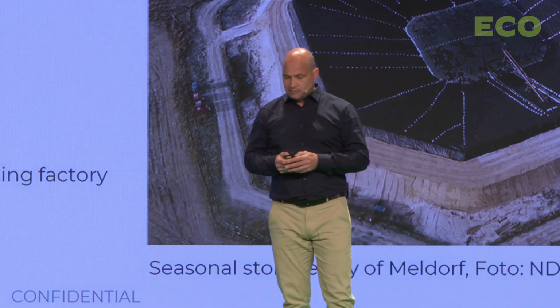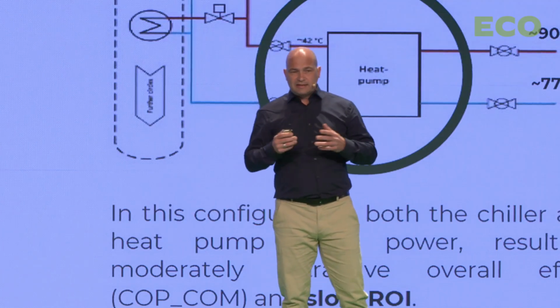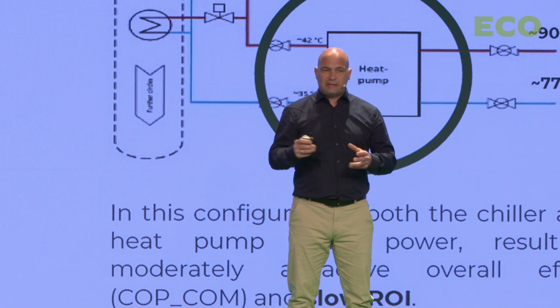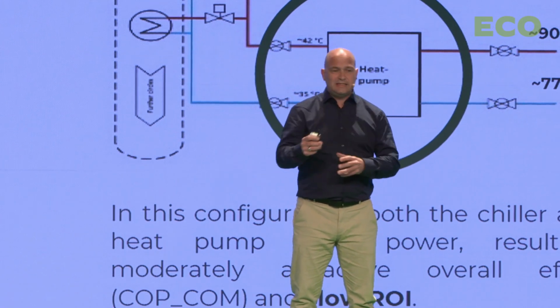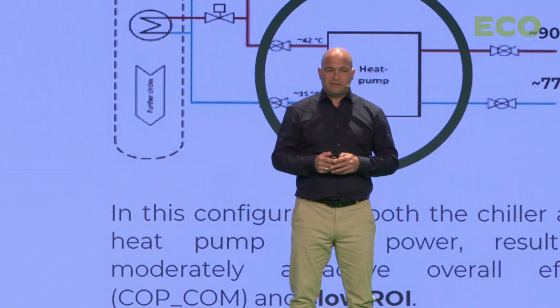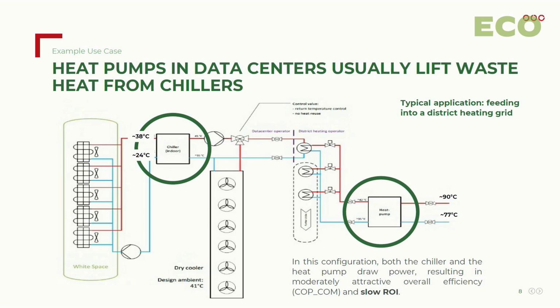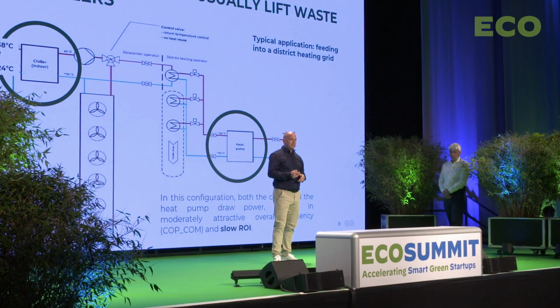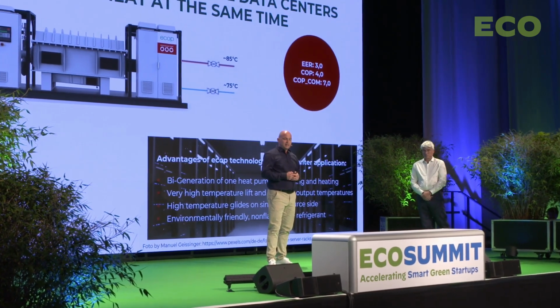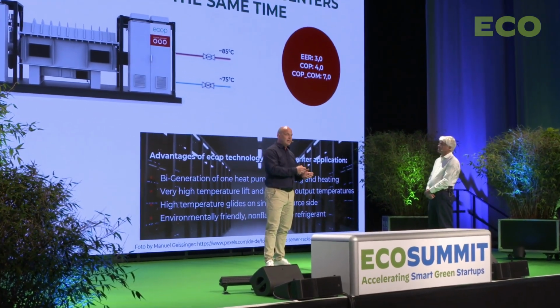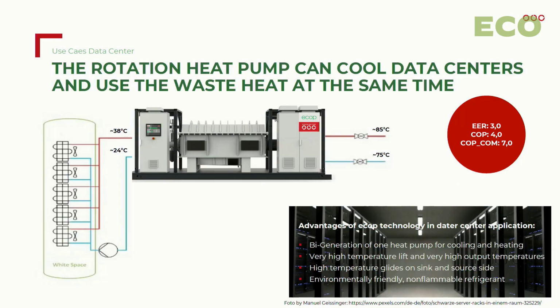Another example is a perfect use case demonstrating that simultaneous cooling and heating is really interesting in terms of business cases. This is a data center where you can have a chiller, and use a heat pump to lift the chiller's waste heat into the district heating grid. But what if you just use one machine for chilling and heat production at the same time?